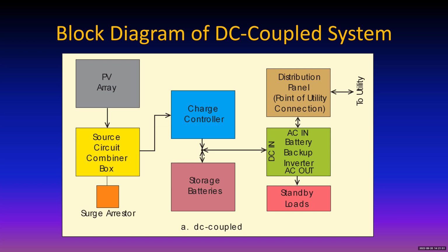You're running thin wires, generally number 10 wire for the electrical folks and anyone else who wonders about wire sizes. You'll run a number of number 10 wire circuits down from the roof into the source circuit combiner box, which may have either 20 or 30 amp fuses, depending on the system. They're then combined, so rather than a typical electrical panel with fat wires coming in and skinny wires going out, you've got skinny wires bringing power into the combiner box and fat wires delivering it to the charge controller.